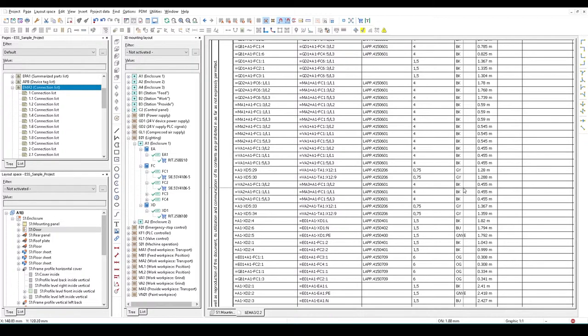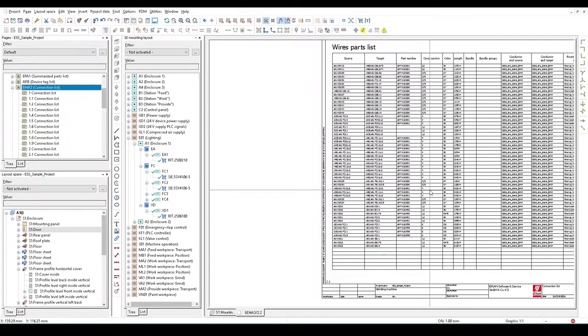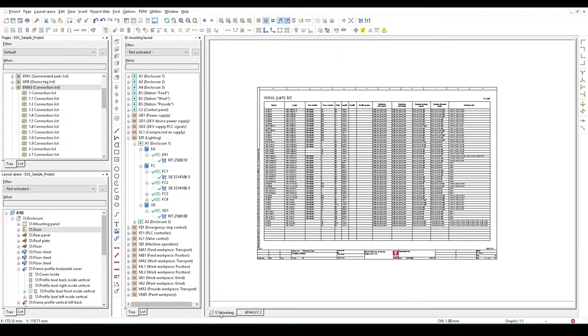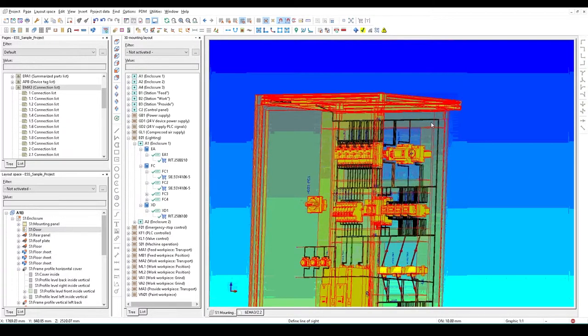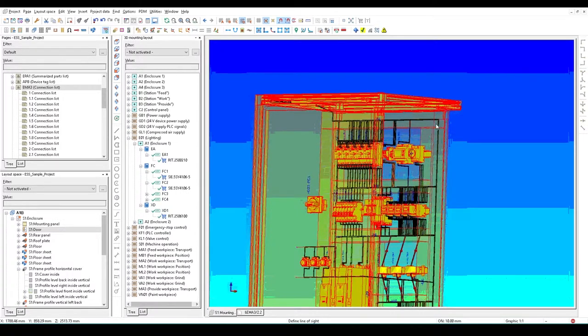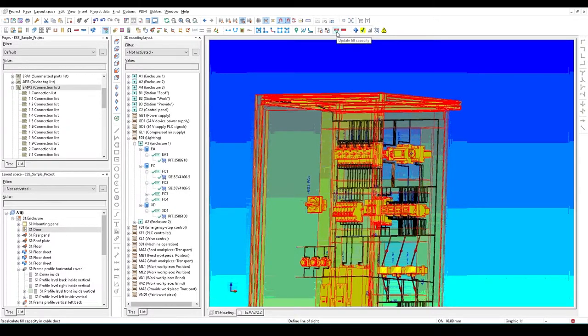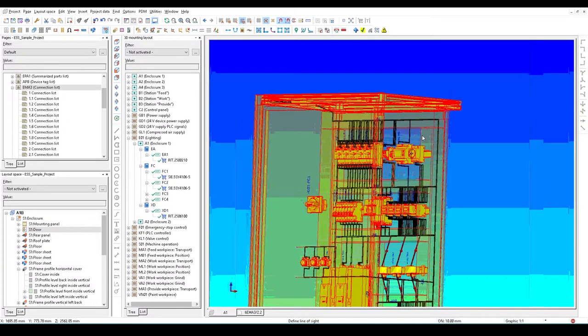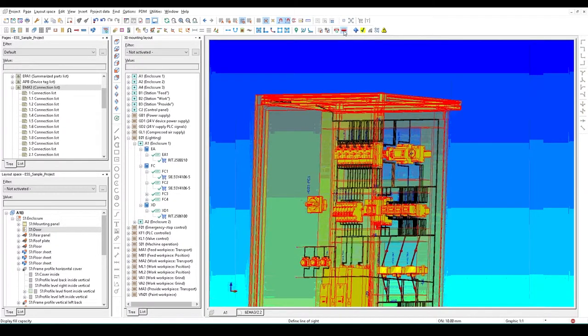I can zoom through and show all the data has gone in there. This is great raw data if they want to use an actual list, but in reality it's not the very best way they can have the data. Other things that can happen is I can update wire trunking. These have dedicated sizes, the wires have dedicated size as well, so I'm able to do something called a fill capacity. If I run an update on the fill capacity, data has changed in the background.